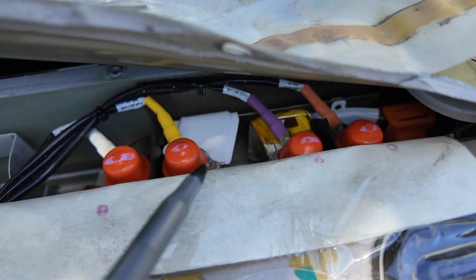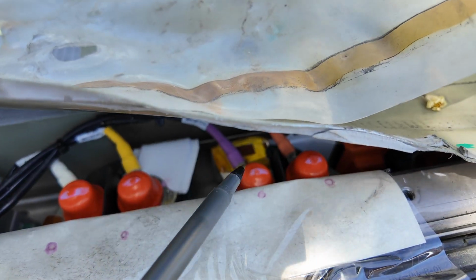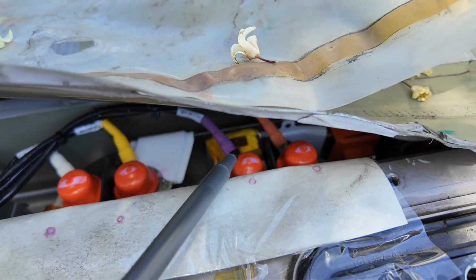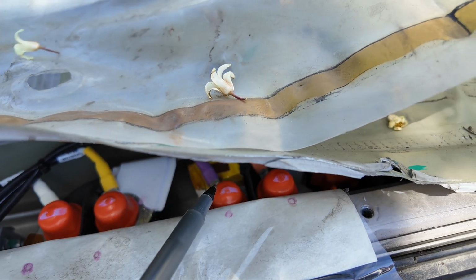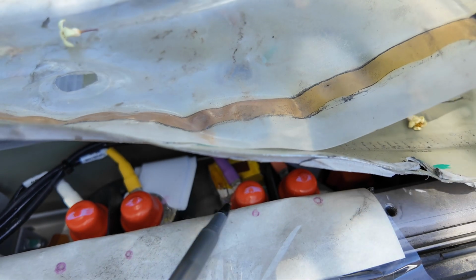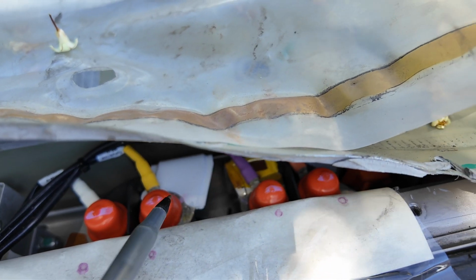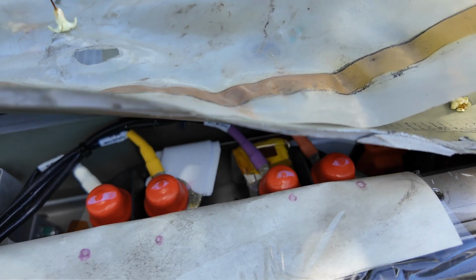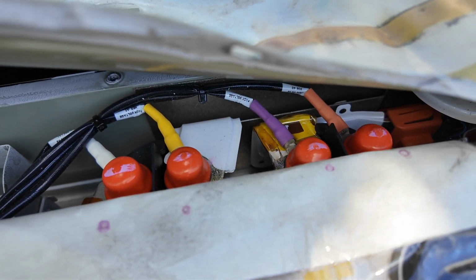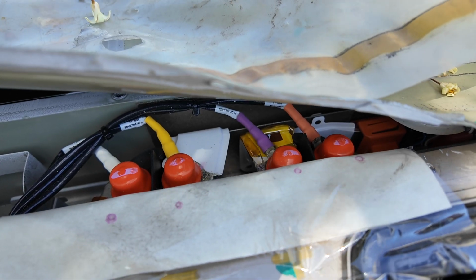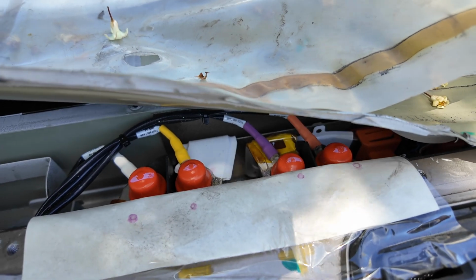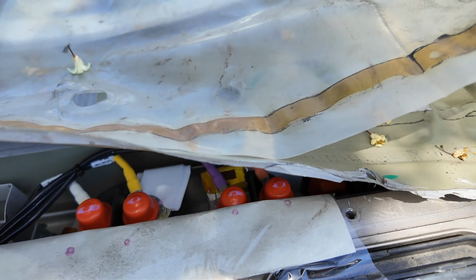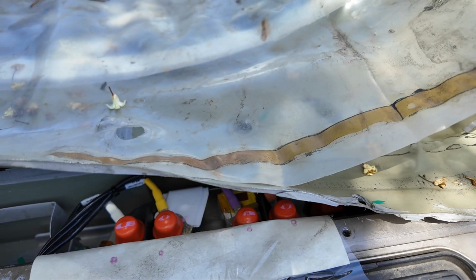The inside is the positive contactor. Also here on this side with the white bus bar connected is the full potential. So if you short out these two terminals here, you would have a full short on the complete battery pack, which is not advisable. Whenever you work on that, wear your safety gear.